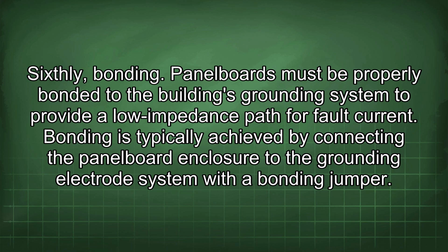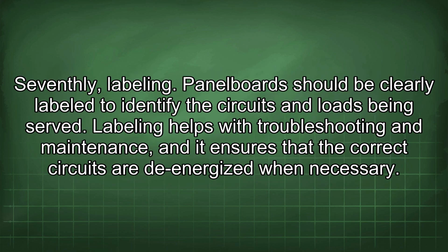Sixthly, bonding. Panelboards must be properly bonded to the building's grounding system to provide a low impedance path for fault current. Bonding is typically achieved by connecting the panelboard enclosure to the grounding electrode system with a bonding jumper. Seventhly, labeling. Panelboards should be clearly labeled to identify the circuits and loads being served. Labeling helps with troubleshooting and maintenance, and it ensures that the correct circuits are de-energized when necessary.